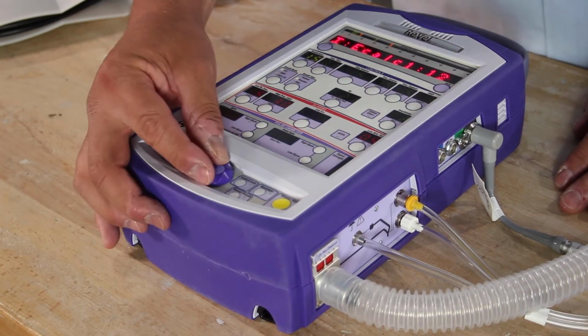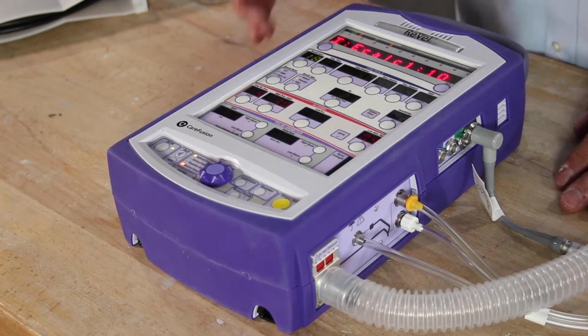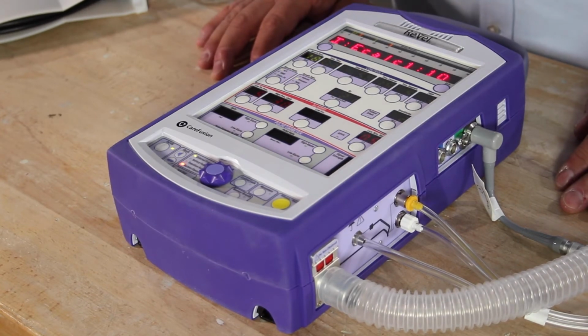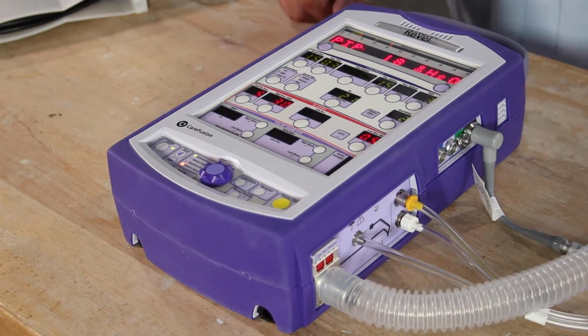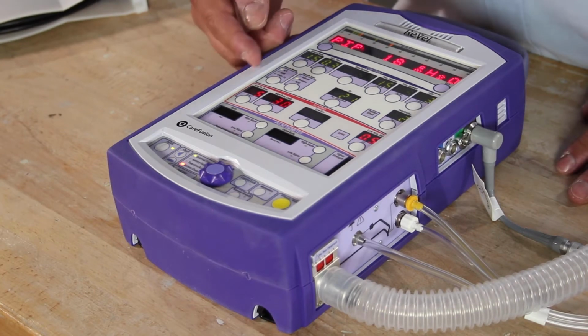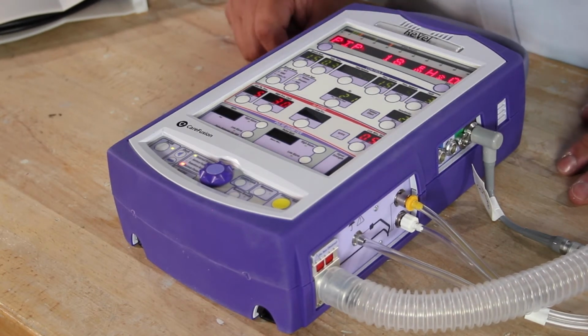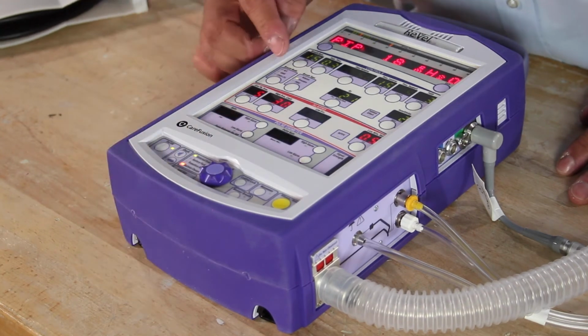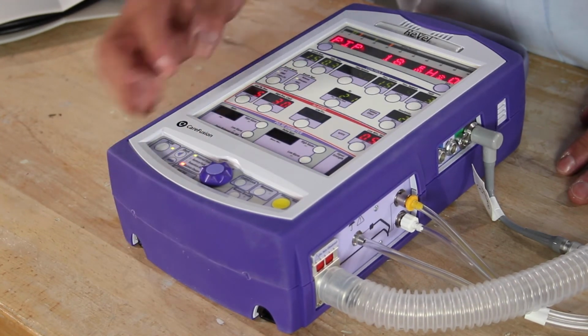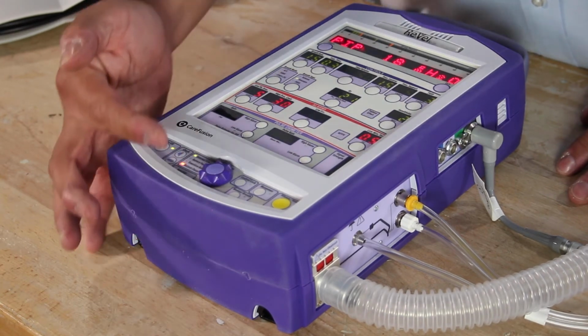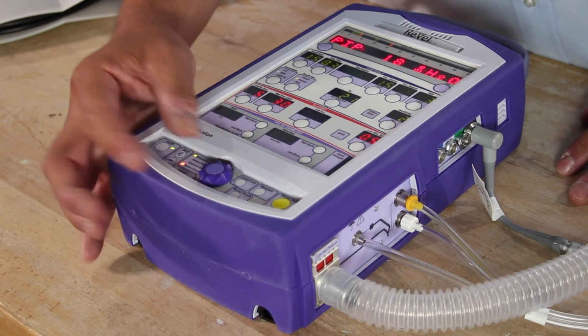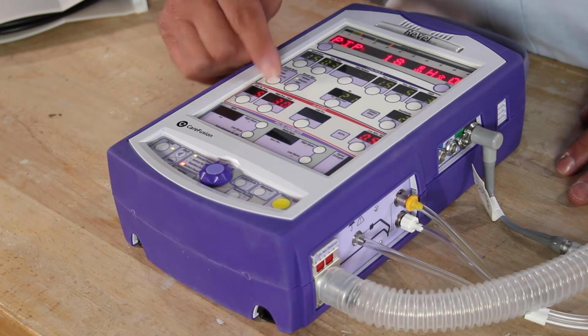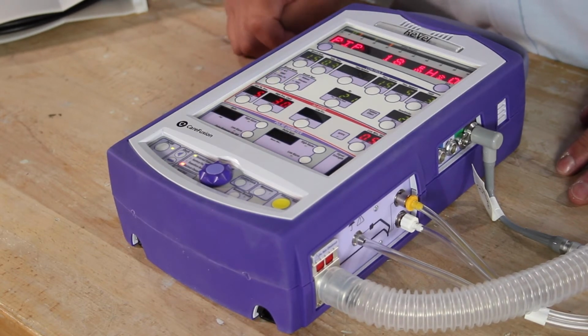Now, press, highlight, and I'm not going to confirm, it'll revert back to the previous setting. There we go. It went back to the previous setting. Okay. Same goes for changing breath modes versus breath types. So press, we're going to get a blink. Use the knob to make the change, so from assist control, SIMV to CPAP plus pressure support. The knob goes up and down to whatever mode we want to use. When we're over the mode we choose, you simply press the button, it highlights. Notice the change.